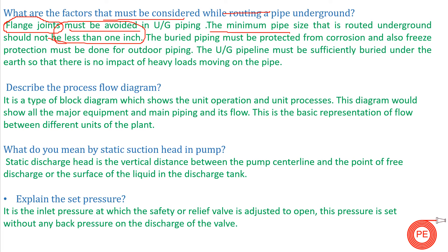The minimum pipe size that must be routed underground should not be less than one inch, because the pipe may collapse because of the earth load. Generally, pipes should be greater than two inches. The buried pipeline must be protected from corrosion, and freeze protection must be done for outdoor piping. When we do underground piping, we provide some protection from corrosion; some epoxy coatings are done on the pipes. The underground piping must be sufficiently buried under the earth so that if there is some heavy load movement, your pipe doesn't get damaged.